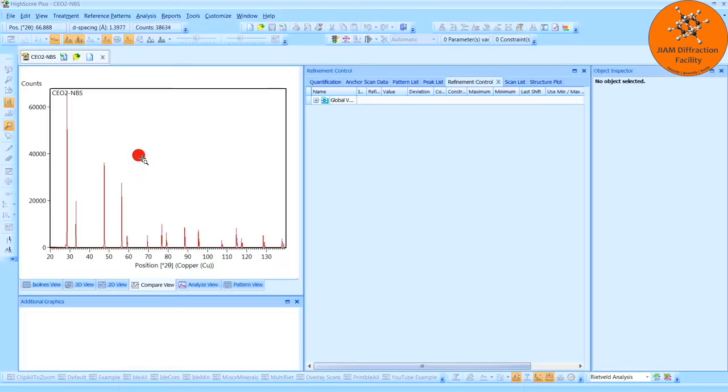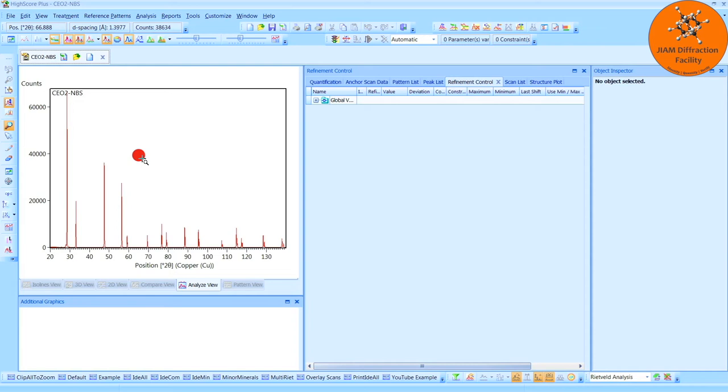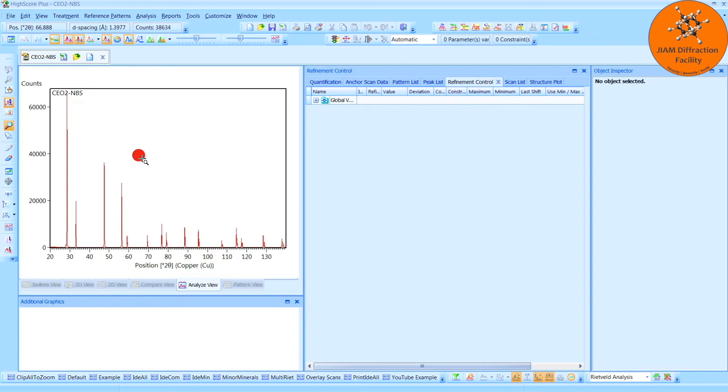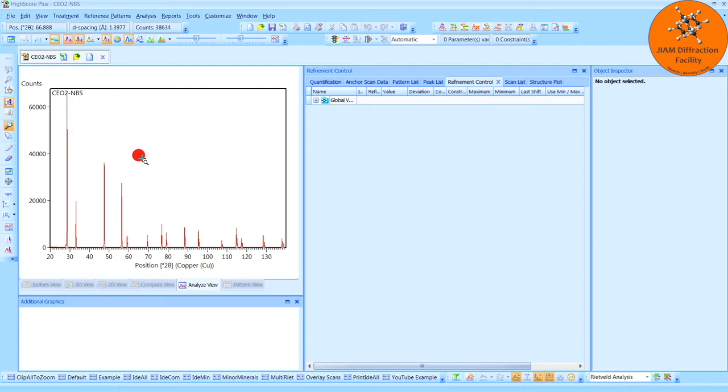Just to make sure it is abundantly clear, you will not use this file if you are analyzing your own samples of interest. I'm only using this file because I am also analyzing those fluorite patterns provided by Panalytical. If you want to analyze your own samples, you will need to get your own line profile standard. Now these are available from NIST, and they are cerium oxide and lanthanum hexaboride, and there are others. But once you get your standard sample, you want to collect a diffraction pattern on it using the same instrument and the same exact optics that will be used for your sample of interest. If any of those optics are different, then your instrumental broadening will be different, and that will make your analysis less accurate.